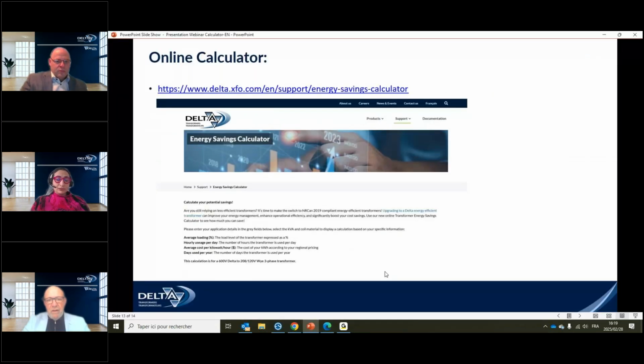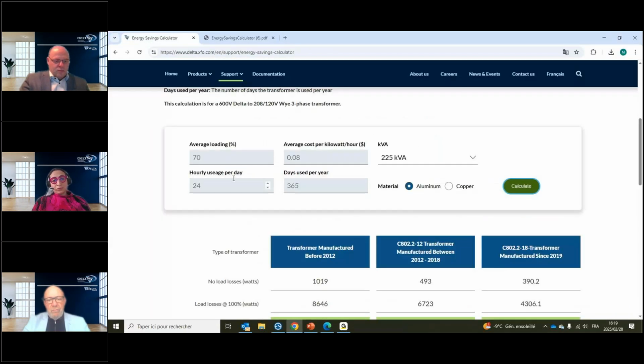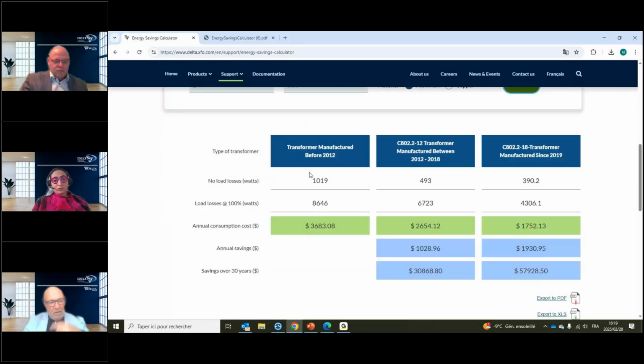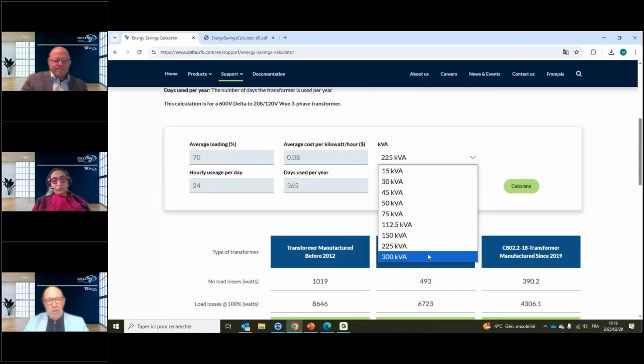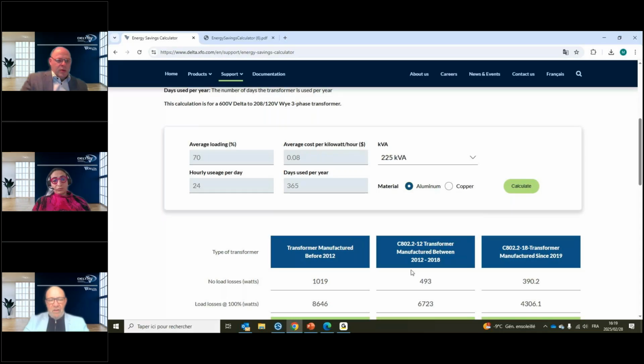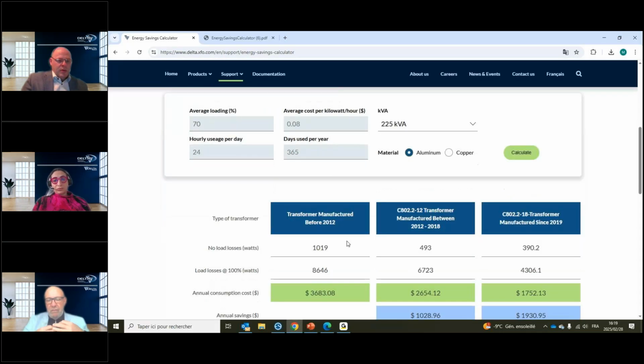we have used the data from Delta Transformer. Mainly behind this, it's a massive Excel calculator spreadsheet, with all the losses for each type of transformer, from 15 to 300 kVA, copper, aluminum, based on the three alterations of CSA. We have used the Delta values. Our engineers dug into our archives and put in all the losses measured on our transformers. So this is not something we have invented. We can prove it by providing test results from transformers built 15 years ago that these are real losses. So this is information and data that you can trust. It's not something we have pulled out of a rabbit hat somewhere.